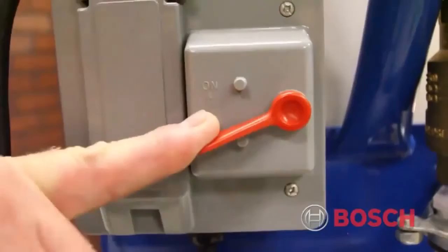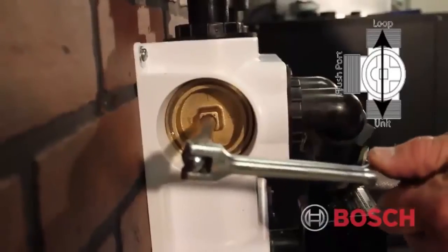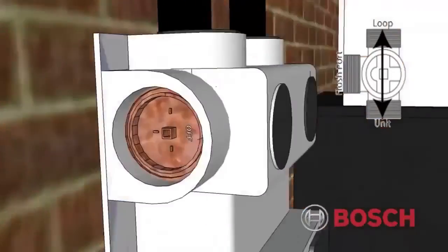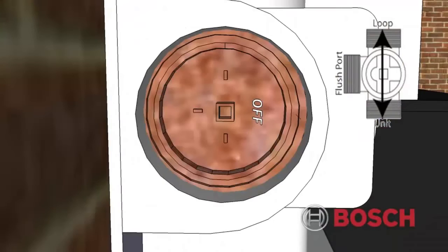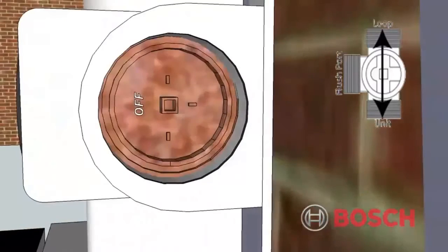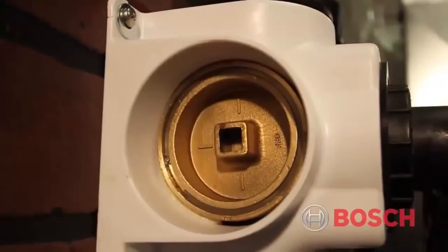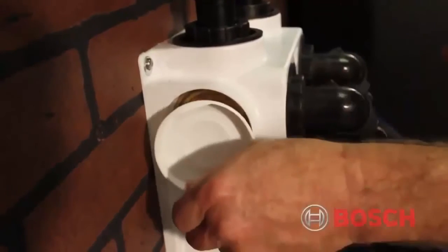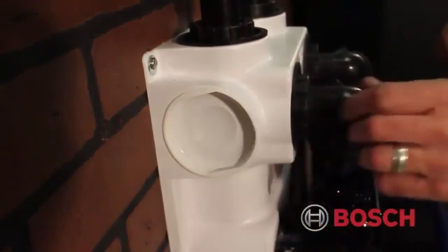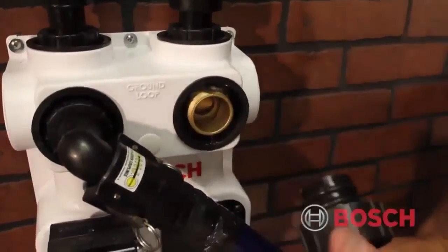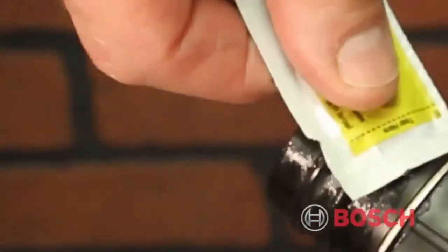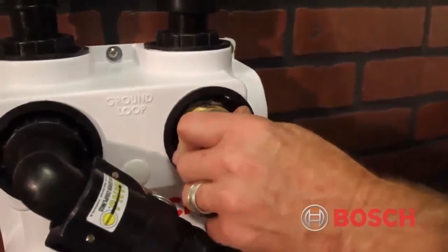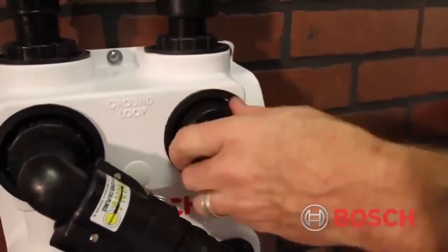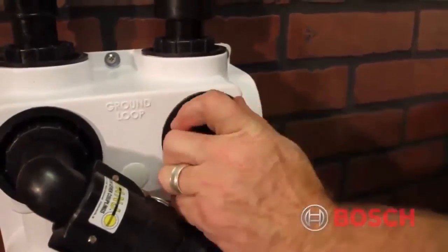Once complete, turn the pump off and rotate the flow center three-way valves to the off position starting with the return side. This will isolate the flush cart from the system. Be careful not to pressurize the loop. At this point, we're finished with the flow center three-way valves and we can reinstall the plugs and protective caps. Remove hoses and flush cart connectors from the flow center. Apply white petroleum jelly to both double O-ring flow center plugs, insert the plugs, and screw on the caps.